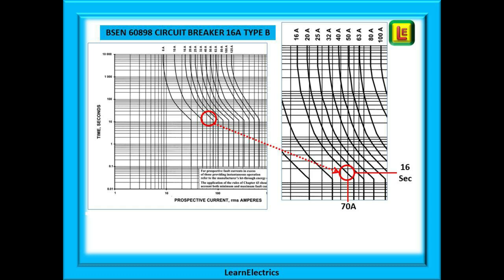Find 70 amps along the bottom row. Follow the vertical 70 amp line up until it meets the curve that is labelled 16 amps as shown at the top. Use a ruler or a straight edge if needed I do. Where the two lines cross follow your eye to the left hand side to find the number of seconds which in this case is about 16 seconds. So a BS EN 60898 Type B breaker with an overload of 70 amps will take 16 seconds to operate.